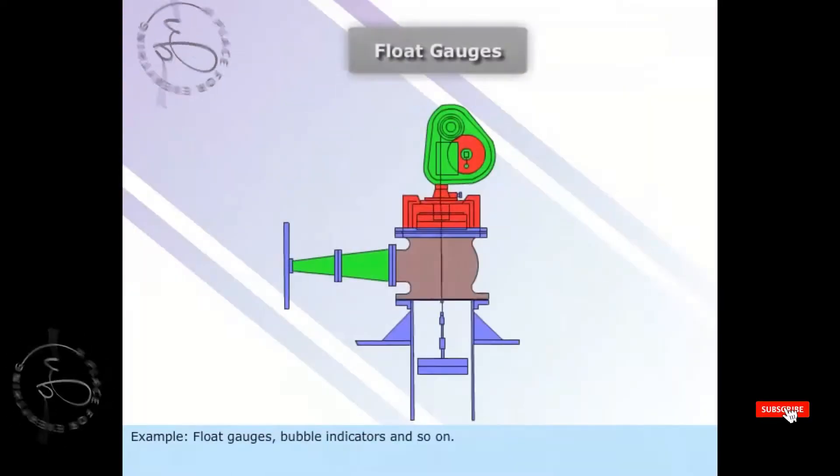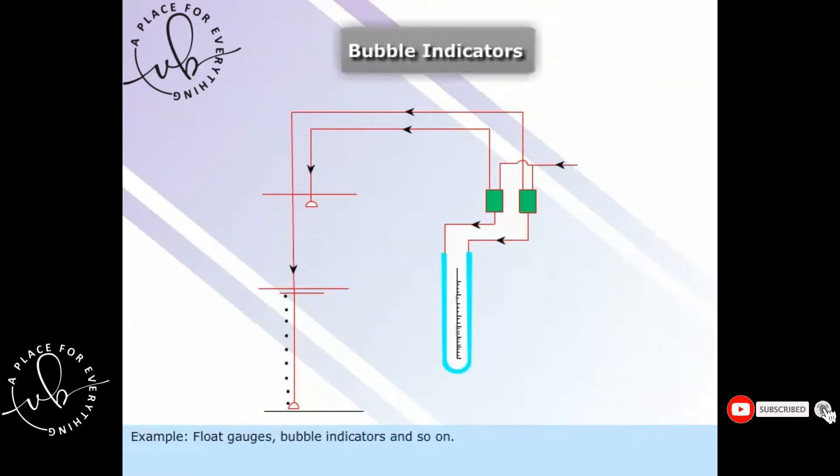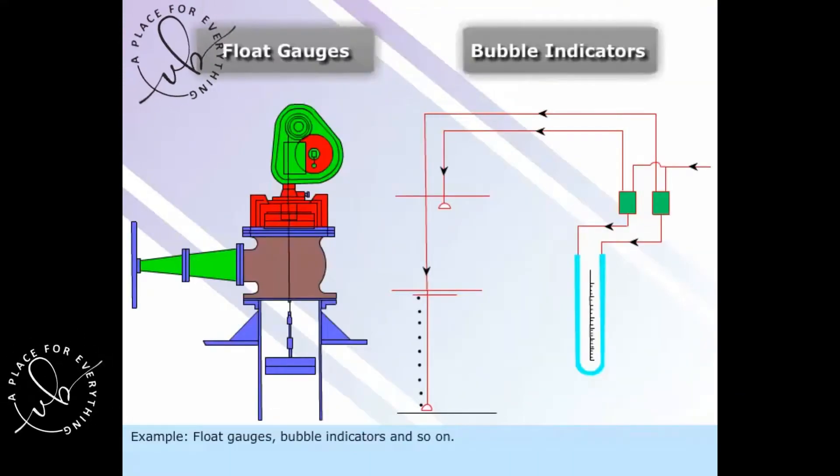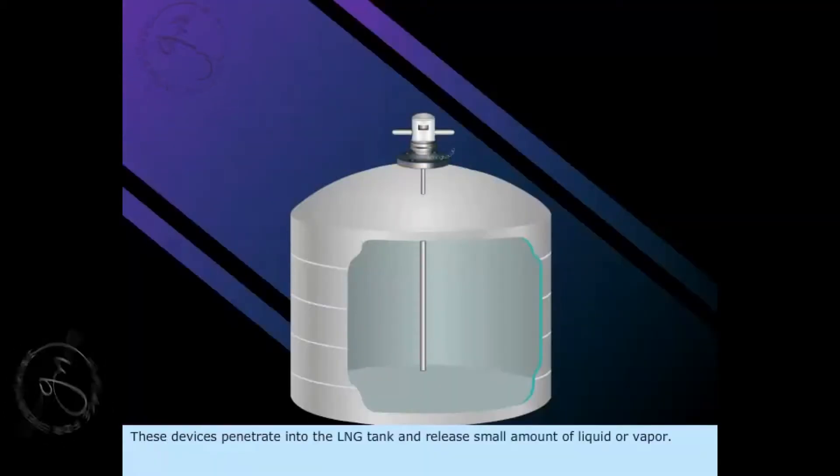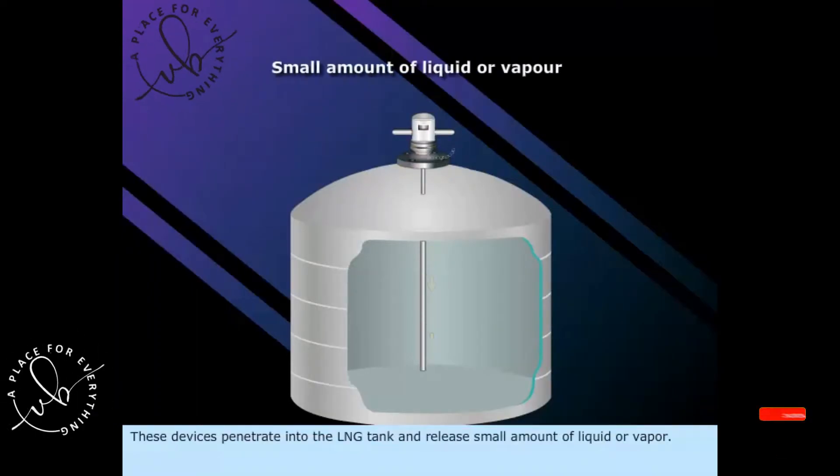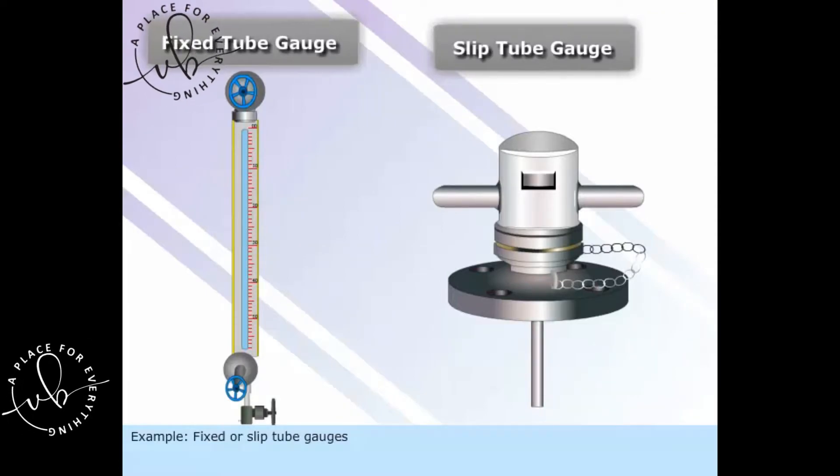3. Closed devices with contact - Float gauges, bubble indicators, and so on. 4. Restricted devices - These devices penetrate into the LNG tank and release small amount of liquid or vapor. Fixed or slip tube gauges.